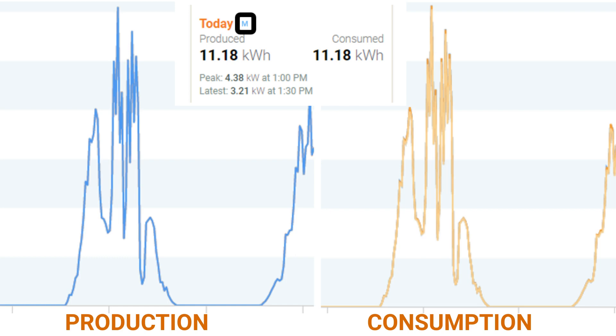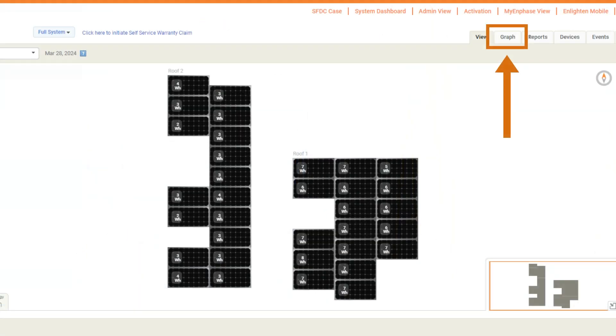When this occurs, there are a few things that you will need to verify to determine the cause of the mirroring and how best to resolve the issue. The first issue that can create mirroring of production and consumption values is if the consumption CTs are not installed properly. To confirm a misinstallation of the consumption CTs, you will need to look into the graph view of the installer portal.